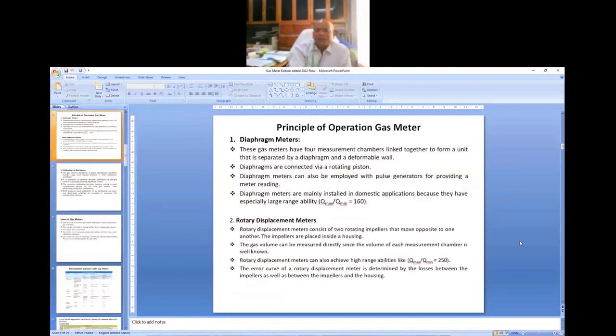Now the principle of operation of gas meters. Number one, the diaphragm meter. These gas meters have 4 measurement chambers linked together to form a unit that is separated by a diaphragm and a deformable wall. The diaphragms are connected by a rotating piston and can also be employed with pulse generators for providing a meter reading. Diaphragm meters are mainly installed in domestic applications because they have especially large rangeability, that is, the ratio of maximum flow rate to minimum flow rate is 160.